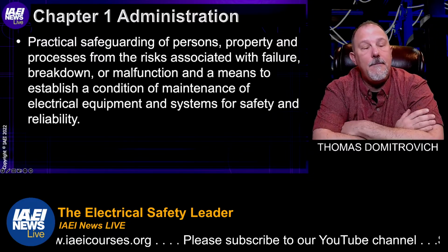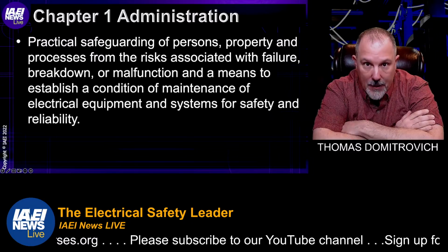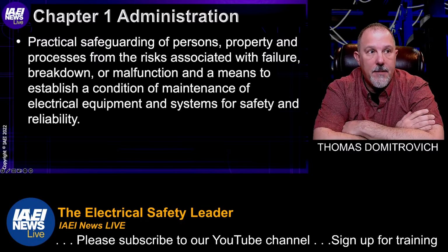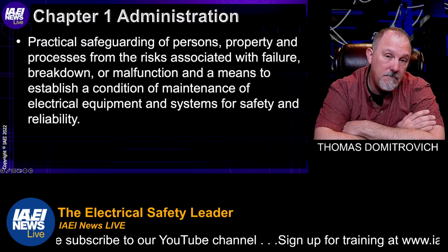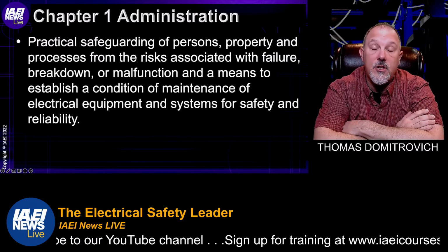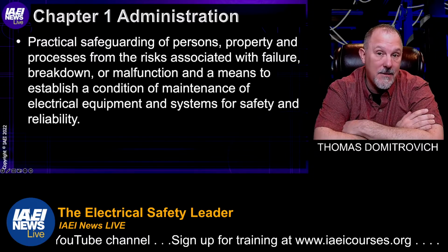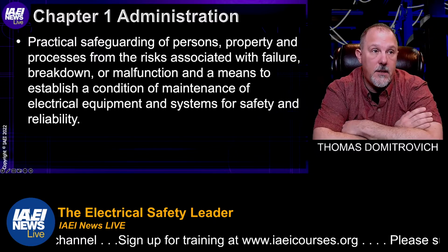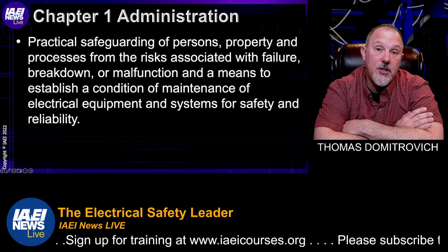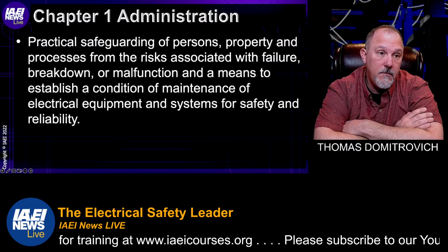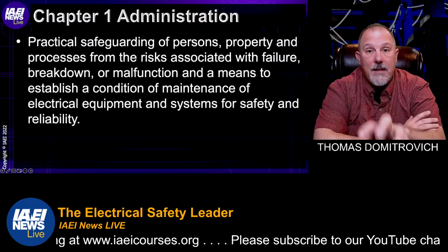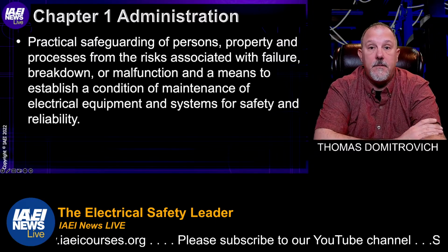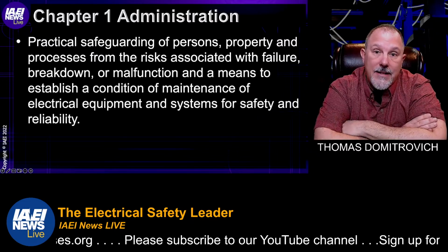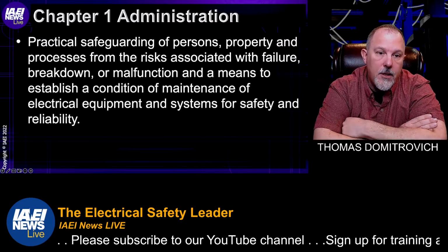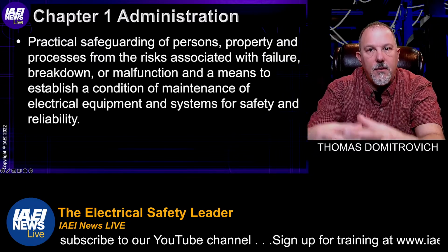Now, when I say systems, when thinking about a panel board, I might think about ground fault protection of equipment, zone selective interlocking as a system, arc flash reduction as a system. There might be systems within energy management - I might have an energy monitoring system inside the panel board. So I have to think about the failure of all of those components.